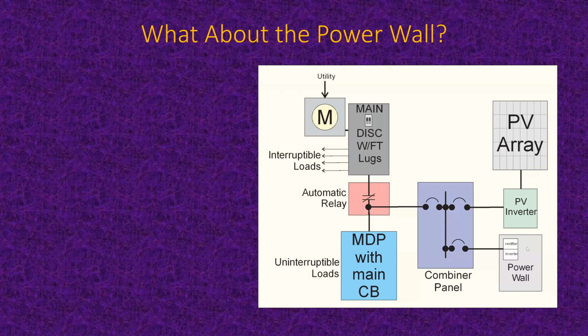Here's your Powerwall down here, and you notice that there's a rectifier and an inverter in it. You have a rectifier because you take AC in from the PV array or from the utility, and that charges the batteries in the Powerwall. Then the Powerwall has its own built-in inverter that sends AC back to the combiner panel.